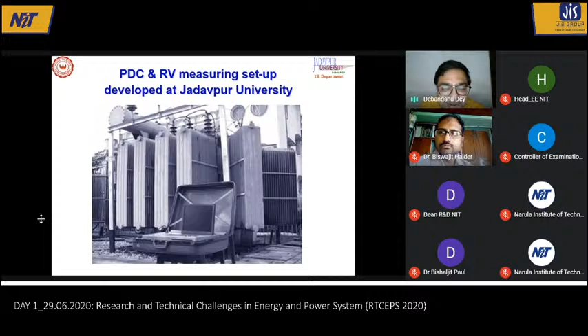These are real life data, and different colors mean different conditions of the insulation, analyzed at different temperatures. The current waveforms vary at different conditions. You can see the conductivity measured in picosiemens per meter, which indicates the condition of the insulation. These waveforms show that data acquisition has a role to play in giving us proper data to get proper information.